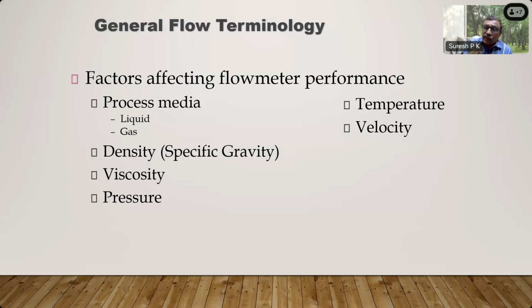So there is a viscosity effect, a density effect, a pressure effect, a temperature effect and a velocity effect. When you are specifying a flow meter, you can buy a proper flow meter only if you provide the proper information on the conditions under which you have to make the measurement. What is the temperature? What is the pressure? What is the viscosity range? What is the velocity, or the flow rate?